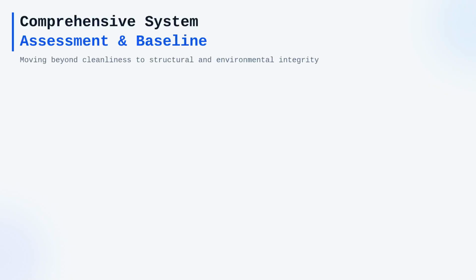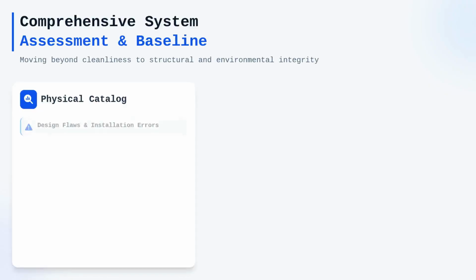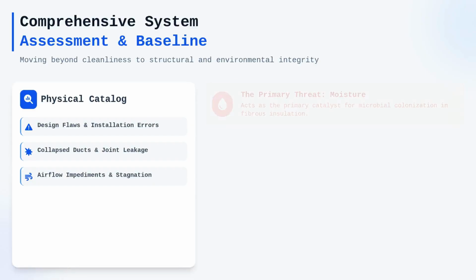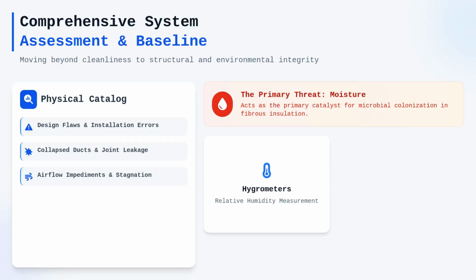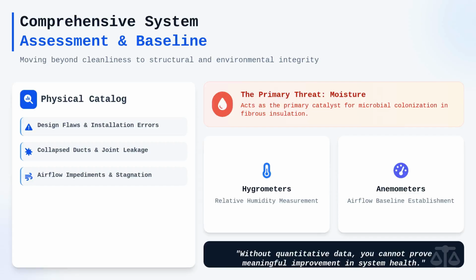Beyond mere cleanliness, your assessment must catalog pre-existing physical damage, design flaws, and environmental hazards. You might encounter leakage at joints, collapsed duct sections, or incorrectly installed components that impede airflow or contribute to stagnant air conditions. Moisture is perhaps the most significant threat we face, as it acts as the primary catalyst for microbial colonization in fibrous insulation. By using hygrometers to measure relative humidity, and anemometers to establish airflow baselines, you gain objective, quantitative data to complement your visual observations.